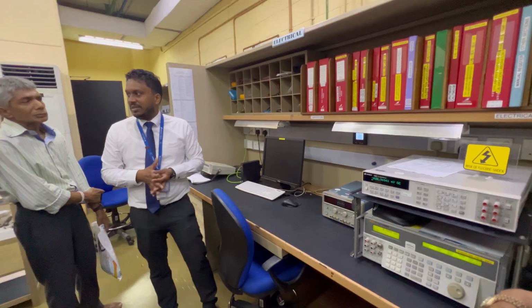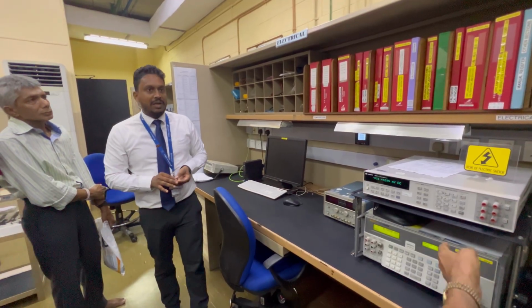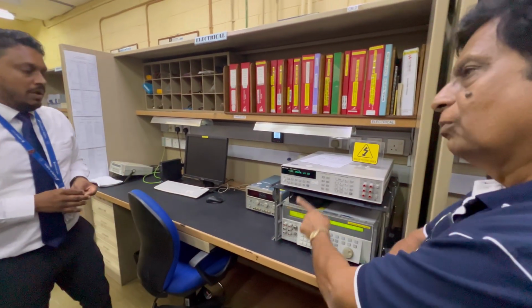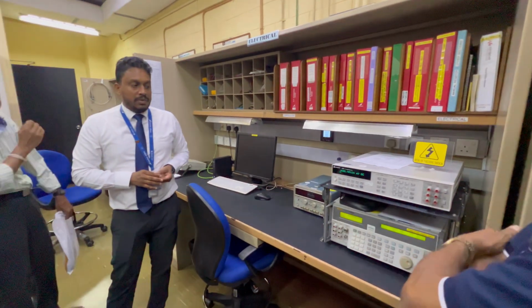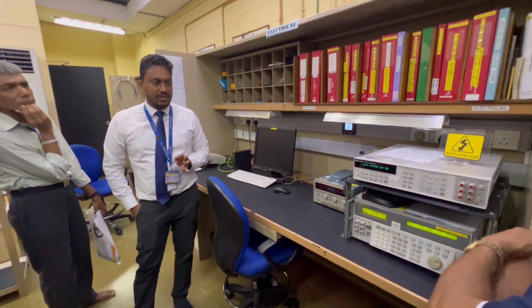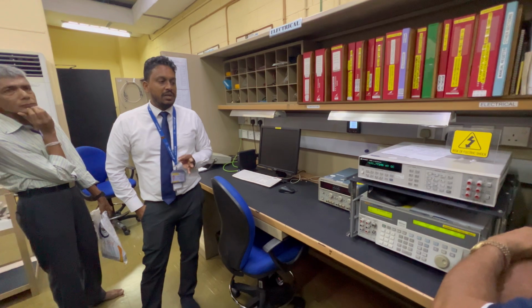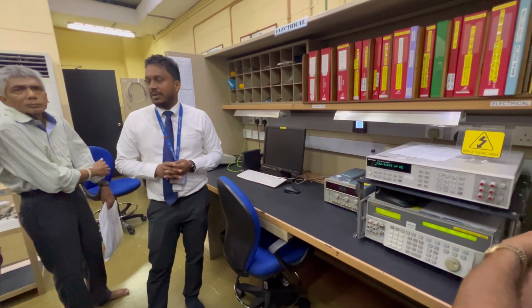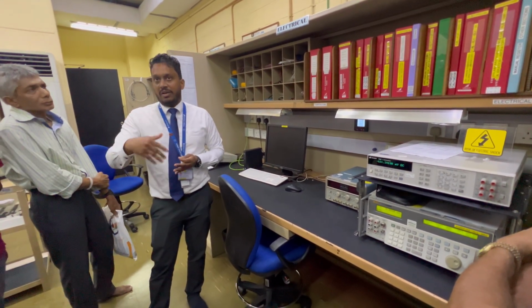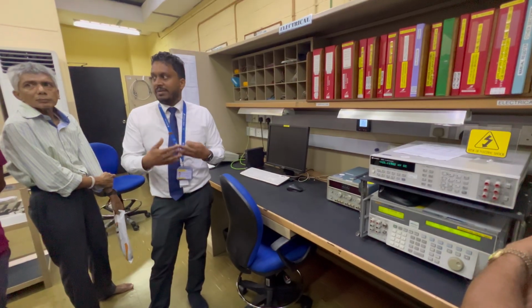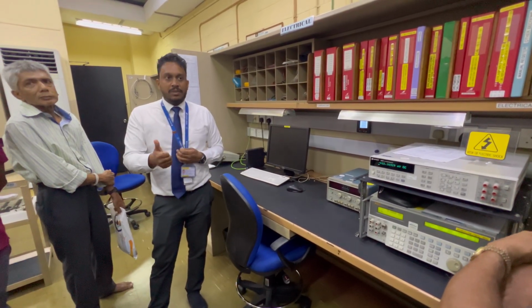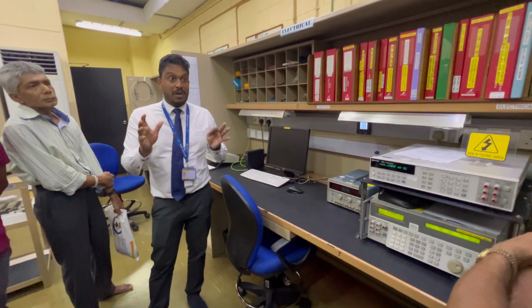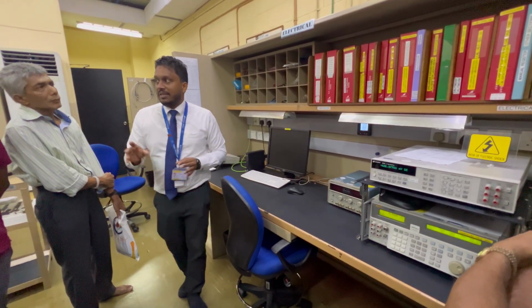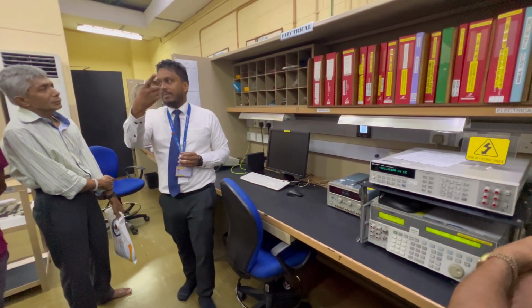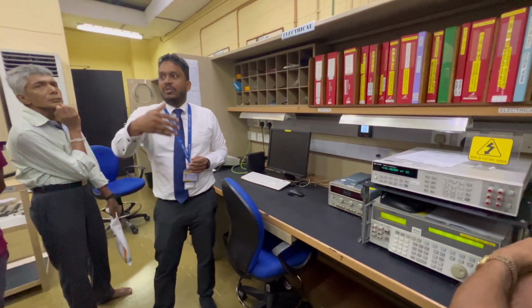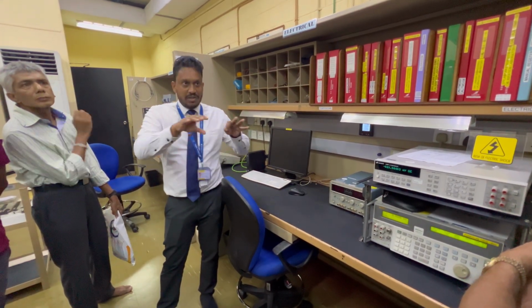So how often do you send these for calibration? It's like this. Sending for calibration is actually a science. You can't do it arbitrarily. The normal method is, if you acquire an item, the rule of thumb is every 90 days if you have a lot of money, or 365 days, you send it to an accredited laboratory. Then you do that cycle for 3 years, and then you check your results.